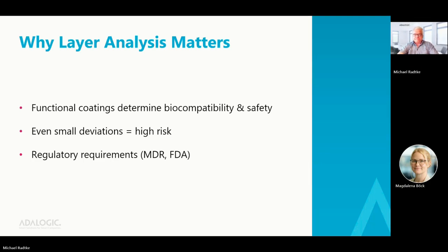The regulatory background from MDR and FDA requires a standardized, traceable, reproducible, repeatable measurement process, which is very important for audits you may have with customers or with the FDA.